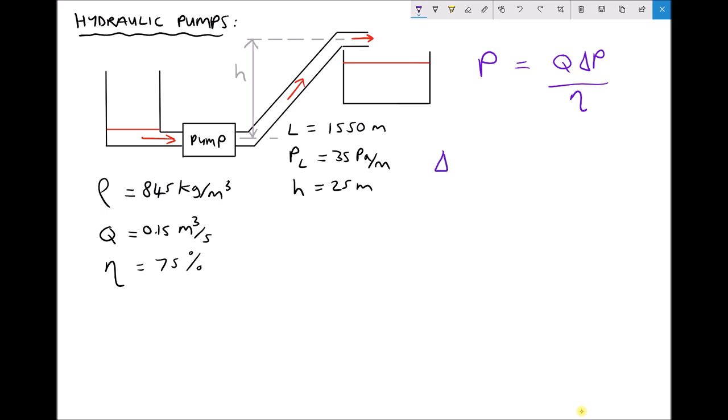The delivery pressure of the pump has two components. First, the pump needs to elevate the fluid through a distance of 25 meters, and the pressure required to do that is density times gravity times height — a formula we've seen on a number of occasions. In addition, there's a pressure loss of 35 pascals per meter of length, and we have a length of 1550 meters, so the additional pressure required is the length multiplied by the pressure loss per meter.